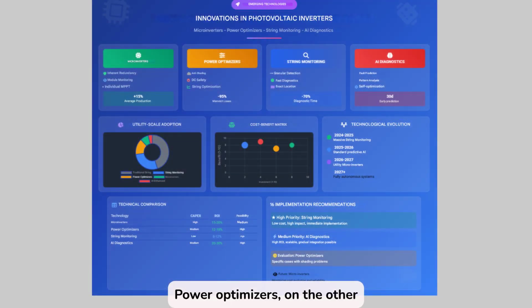Power optimizers, on the other hand, operate within the DC system, where they improve safety, enable rapid shutdown in emergencies, and, above all, correct imbalances between modules that cause mismatch losses. In plants where strings are not perfectly balanced, their application can reduce these losses by up to 95%, justifying their analysis as a viable solution in certain cases. However, their implementation must be carefully evaluated, especially if there are budget constraints or if the design is already homogeneous.